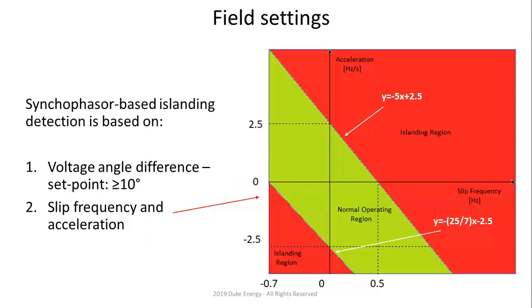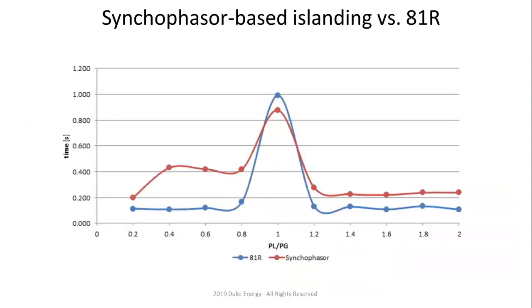As long as you're within the green, that's a normal operating region, right? It doesn't mean that the voltage would not take you out from the standpoint of islanding. But this is the synchrophasor-based islanding. This is just the frequency section on the right side. So you write these equations, you implement it in the field yard, and essentially here's what happens. This shows synchrophasor-based islanding versus 81R. Remember, we have 81, we have 27, 81U, 81O. We have 81R. Now we have synchrophasor-based islanding.